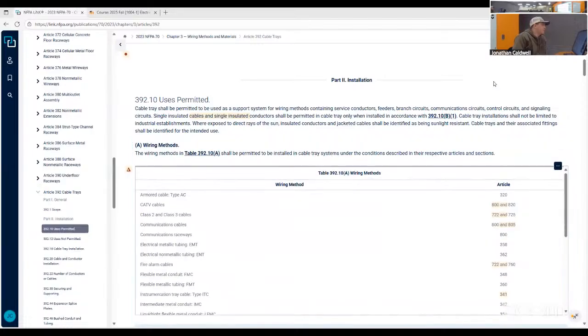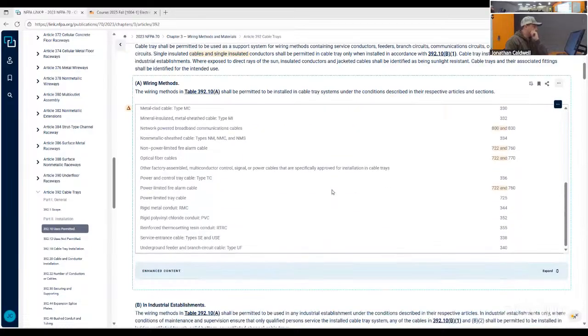So, use is permitted. Cable trays shall be permitted to be used as a support system for wiring methods containing service conductors, feeders, branch circuits, communication circuits, control circuits, and signaling circuits. Single insulated cables and single insulated conductors shall be permitted in tray only when installed in accordance with 392.10(B)(1). Cable tray installation shall not be limited to industrial establishments. Where exposed to direct rays of the sun, insulated conductors and jacketed cables shall be identified as being sunlight resistant. Cable trays and their associated fittings shall be identified for the intended use. And it goes through the list of wires and all sorts of stuff that you can do.